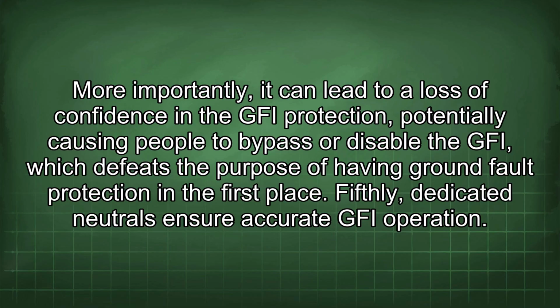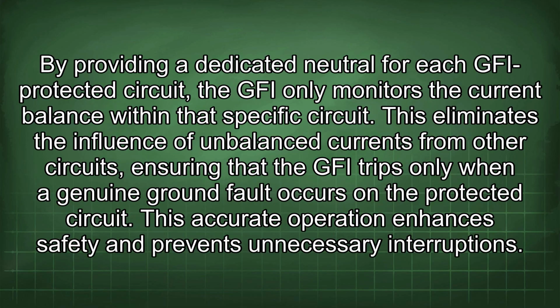Fifthly, dedicated neutrals ensure accurate GFI operation. By providing a dedicated neutral for each GFI protected circuit, the GFI only monitors the current balance within that specific circuit. This eliminates the influence of unbalanced currents from other circuits, ensuring that the GFI trips only when a genuine ground fault occurs on the protected circuit. This accurate operation enhances safety and prevents unnecessary interruptions.